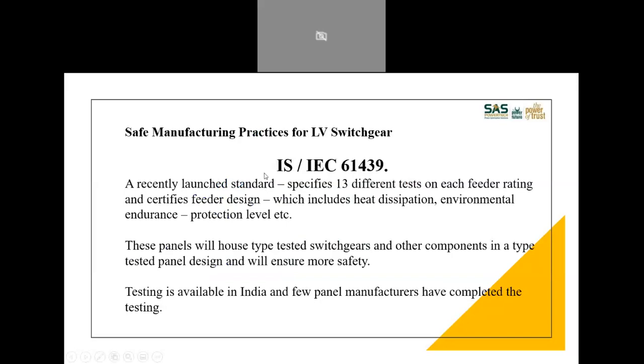Now let us come to some safe manufacturing practices for LV switchgear. See, this IEC 61439 was introduced about 3-4 years back, but now it has started becoming popular even in India. We have so many system houses of leading switchgear manufacturers getting certified for 61439 now. There are about 13 different tests which a manufacturer has to conduct on each rating of the feeder. I mean, suppose I get it certified for a 5 HP starter or isolator and a 100 HP starter or isolator, things like that. All those feeder designs, if you get certified, have to undergo these 13 different tests.